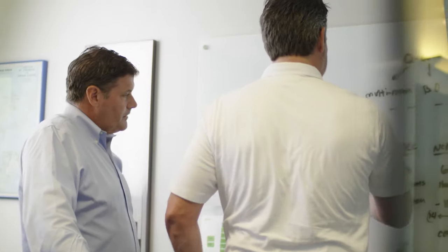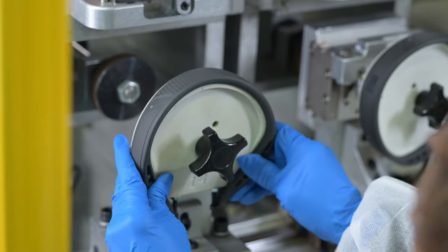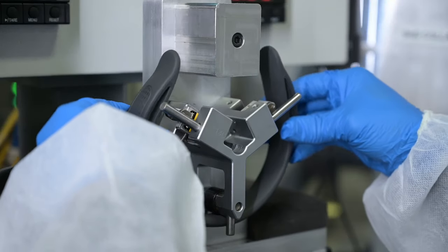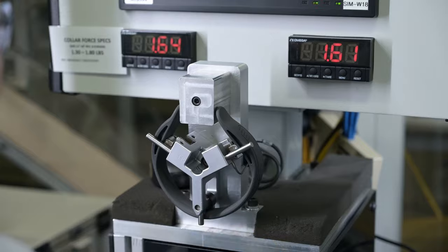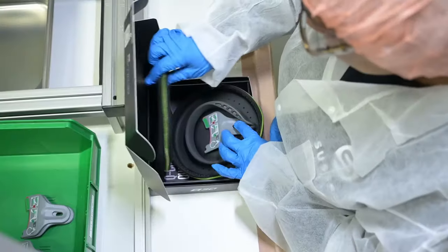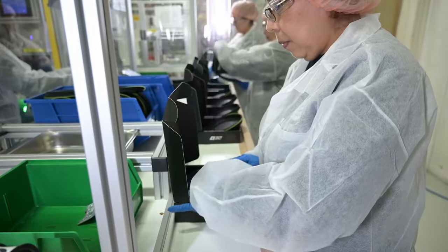The Q-collar actually contains a stainless steel insert on the inside, which is what provides the compressive force against the neck. We then take an elastomeric plastic and over mold it onto the metal, and that provides the protective barrier between the stainless steel insert and the user. It also makes sure that we apply pressure in the correct area — the correct zones — targeting the sternocleidomastoid muscle in a way which compresses the jugular vein, without hindering or interfering with activities.